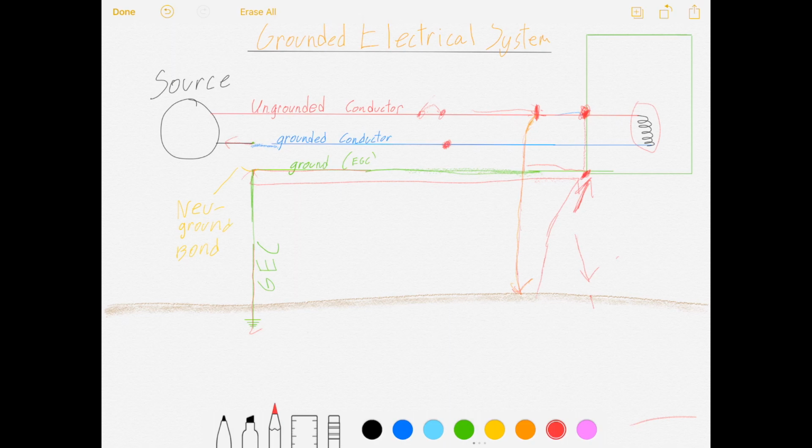And if you were to accidentally touch it, and you're standing on a conductive surface, then now the current would flow through that ground and back and into the earth, and then through your body to where you're touching that grounded conductor and back to the source. And again, we have the same problem that we had with either of the other two grounding omissions. So that's why it's important to have all the parts.